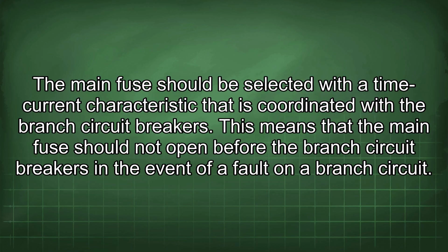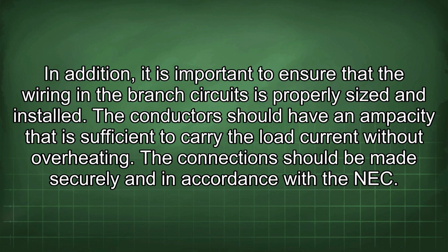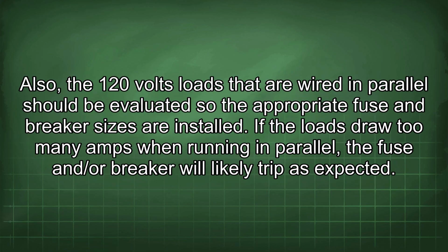In addition, it is important to ensure that the wiring in the branch circuits is properly sized and installed. The conductors should have an ampacity that is sufficient to carry the load current without overheating. The connections should be made securely and in accordance with the NEC. Also, the 120 volt loads that are wired in parallel should be evaluated so the appropriate fuse and breaker sizes are installed. If the loads draw too many amps when running in parallel, the fuse and or breaker will likely trip as expected.